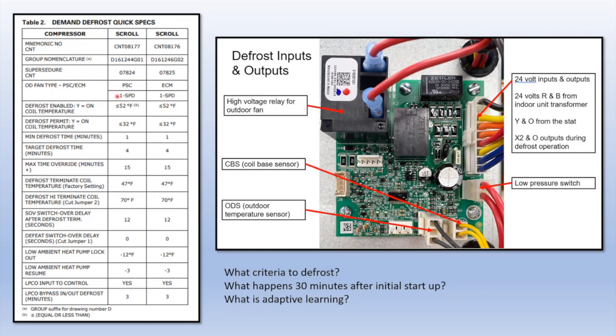Another thing I want to show you guys is the chart that you can find in service facts. So in that envelope in the service door, there's service facts, and you'll see this chart somewhere in the middle where you'll see defrost is only enabled when it's less than 52 Fahrenheit outside. That's because if it's less than 52 Fahrenheit, you could potentially be frosting up your coil, right? Because that coil could be as much as 20 degrees colder than ambient, which is freezing. So it can't go into a defrost when it's above 52 Fahrenheit. It also can't go into a defrost unless the coil is colder than 32 Fahrenheit, because that's the temperature you can develop frost on it.